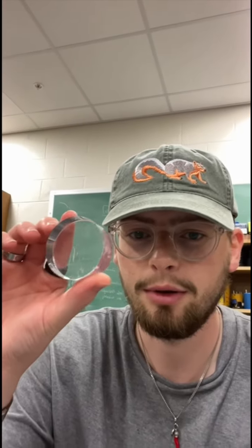Or if you want to have a very good timing resolution, say you have an experiment where you want to measure things that both happen in two detectors at the exact same time. We call that a coincidence measurement. Then you need a detector that can very accurately measure the timing of those two occurrences and then see if they have the same or different timings. So in that case, you might decide to go with a barium fluoride crystal for your detector.